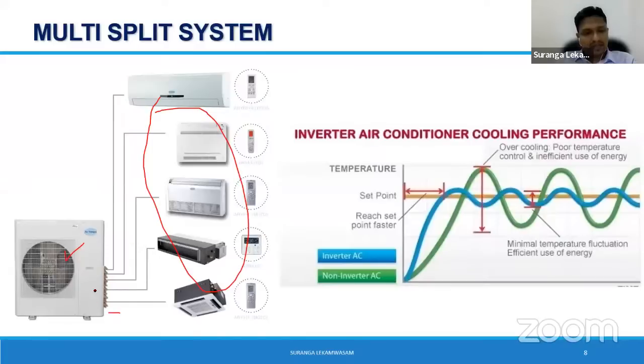That is because all your expansion devices are at the condenser unit, right? So you need to run a bunch of ref pipes. But again, you can see when you feed multiple indoors with a single compressor, the compressor should vary the supplied cooling capacity as per the demand, because I should be able to run only a single unit. So then eventually your compressor has to run on an inverter.